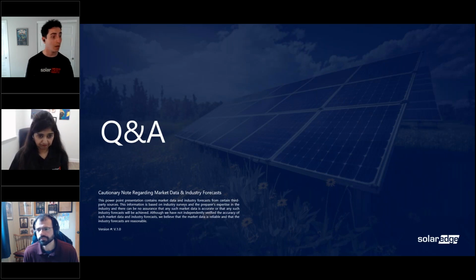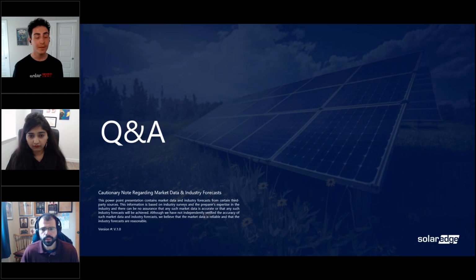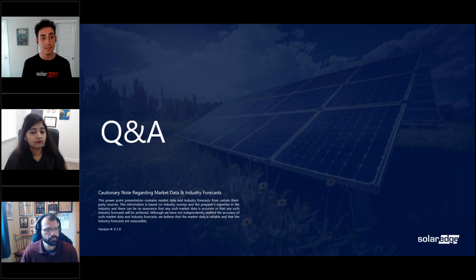Good question, John. So I would encourage you to check out some of the listings of different racking manufacturers for UL 3741. There are definitely a few of them out there, with 3741 listings that are using zip ties as an integral piece of the wire management and essentially maintaining certain gapping distances from conductive parts of the racking to the cabling within the array. So I would recommend definitely checking that out.